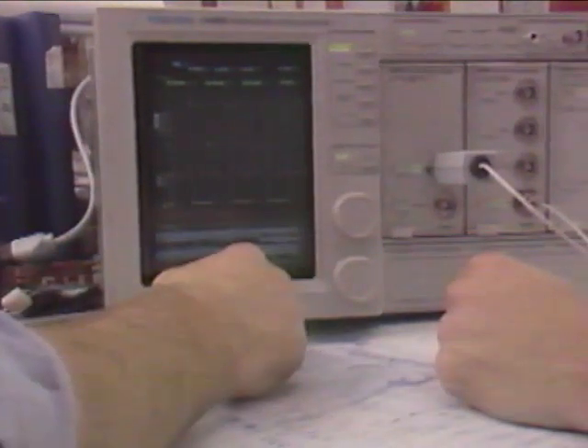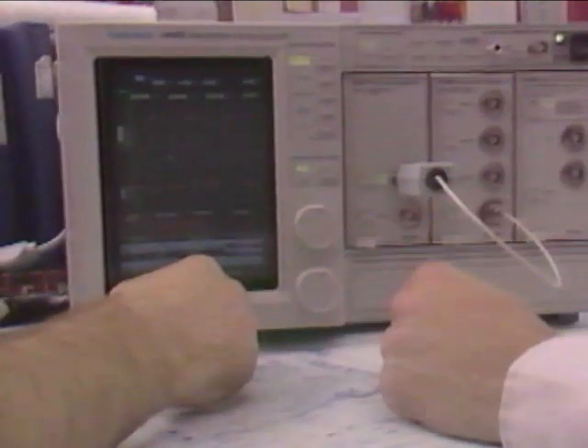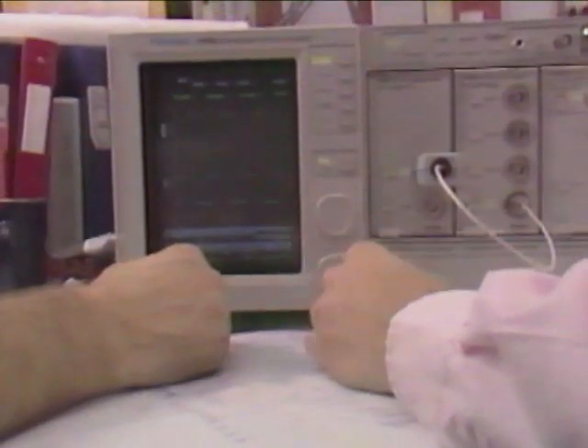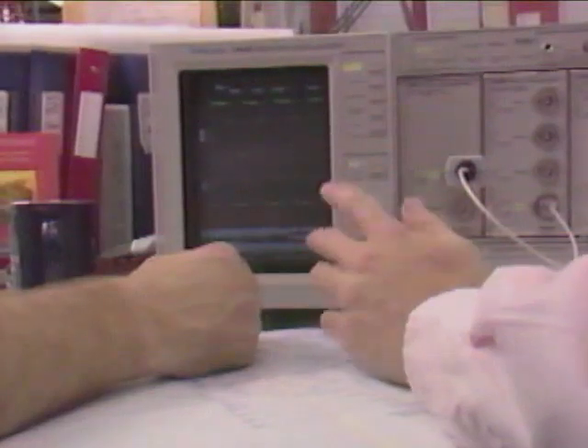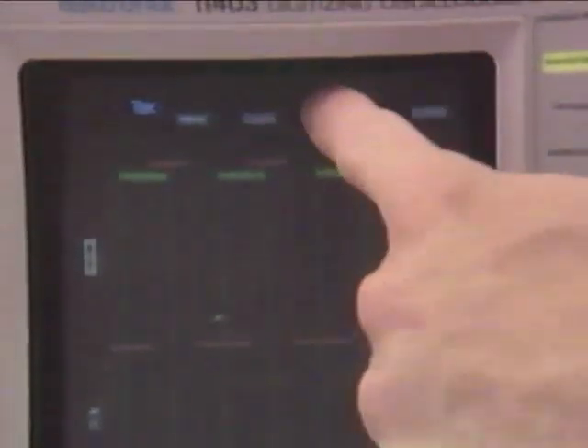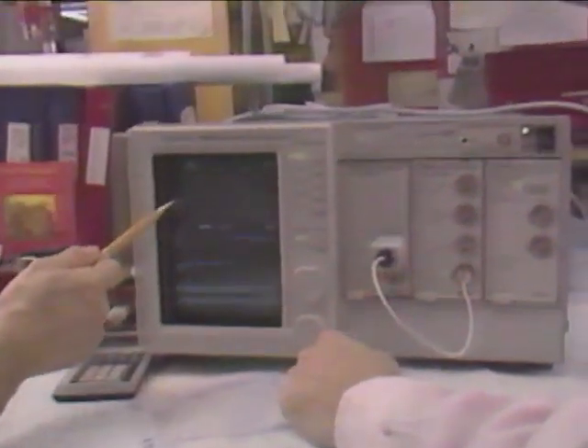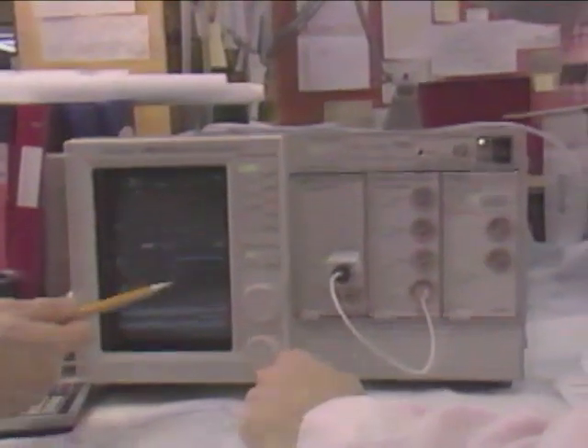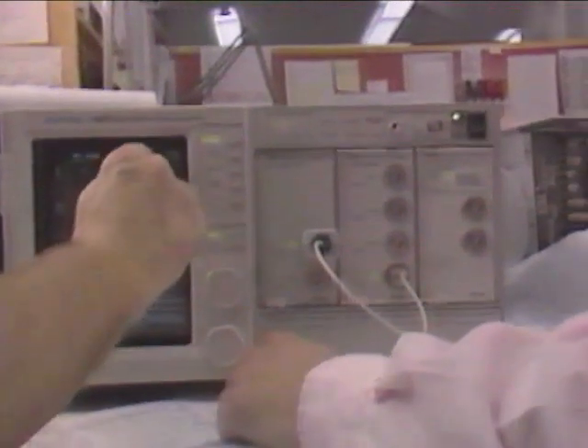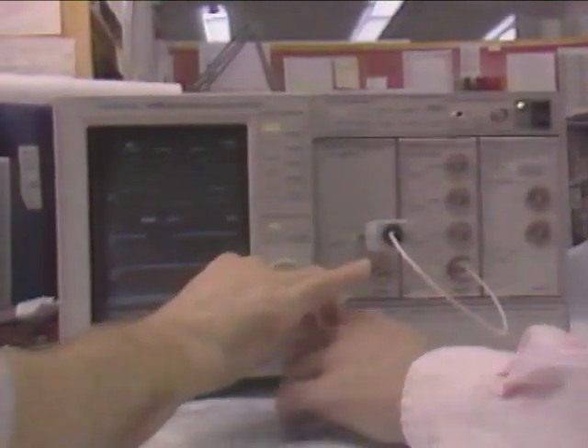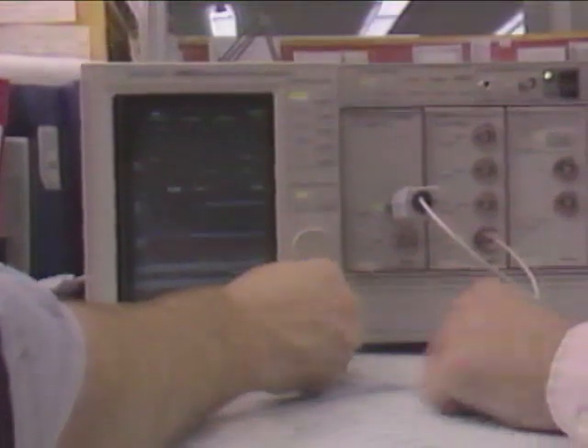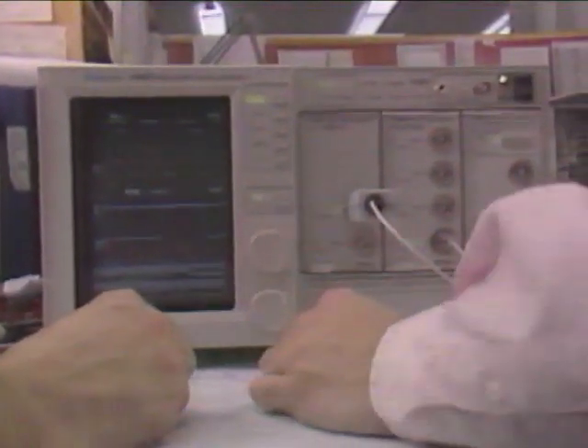How many waveforms can I bring up at one time? Well, you can acquire up to 12 and display up to 8, including things- Then what rigmarole do I go through to reassign the knobs to a new waveform? Well, just like this. Just like that, huh? Yeah, just touch it. The selected waveform brightens and then all associated readouts are in matching color. Oh, and by the way, just touch this window icon here to open up a more detailed close-up sample of a selected portion of the waveform. In fact, you can zoom into 10 picosecond per div sweeps. Great! And I can see exactly what part of the main trace is being highlighted. Well, bring up a second window if you like. It's more or less like the delayed sweep on an analog scope, so you can really dig into detail.